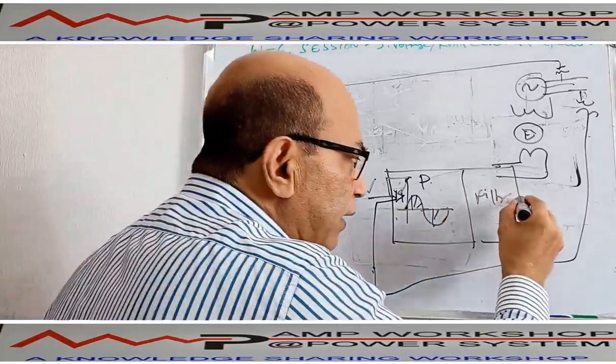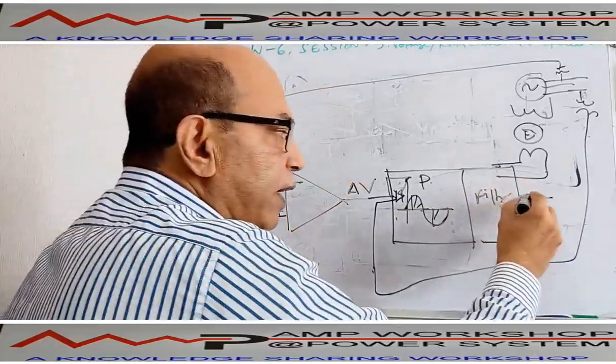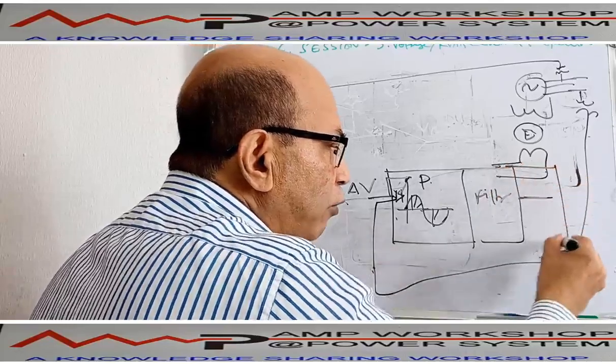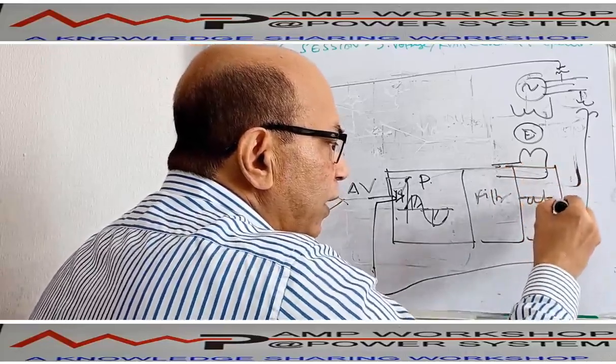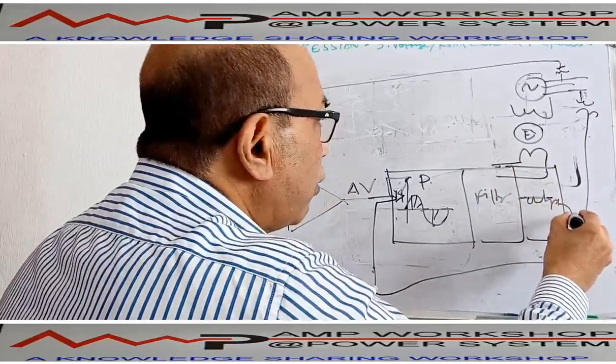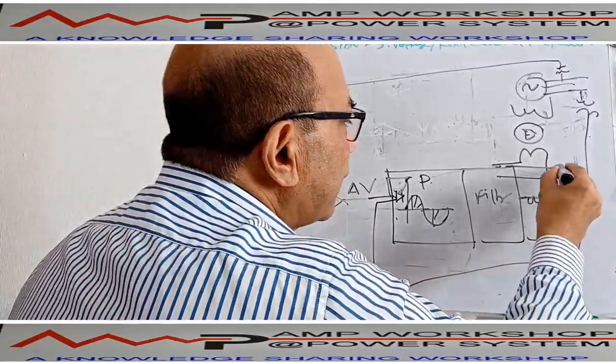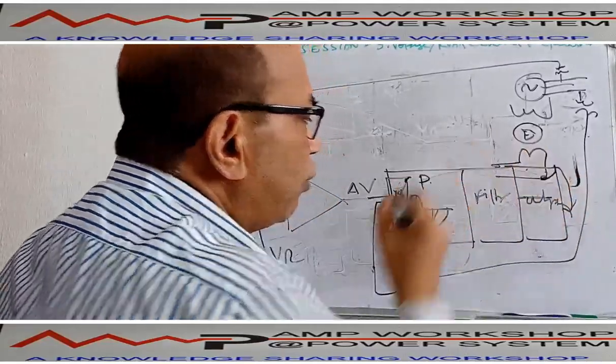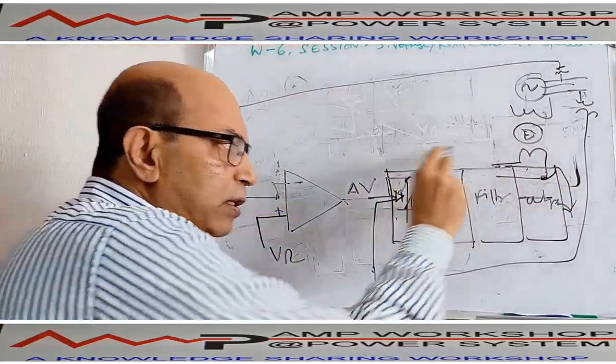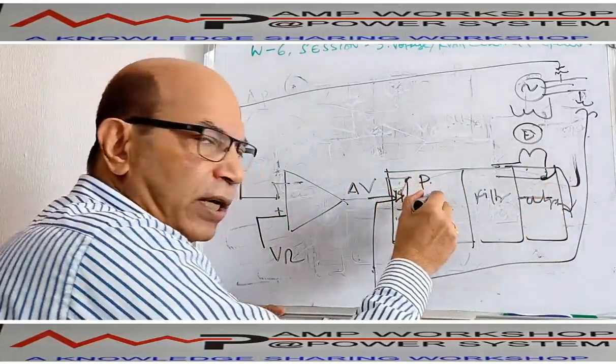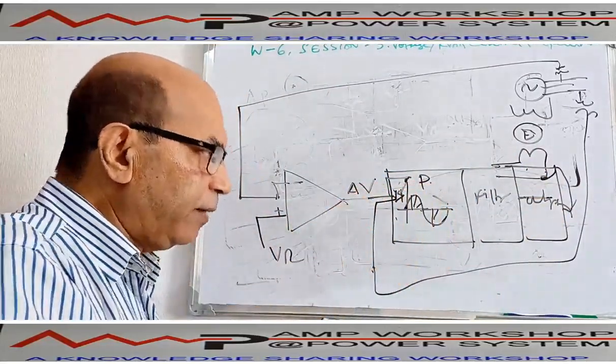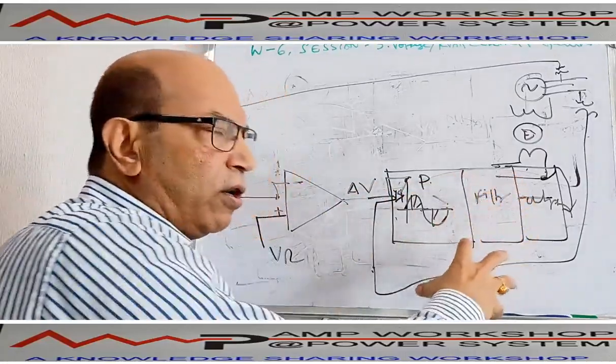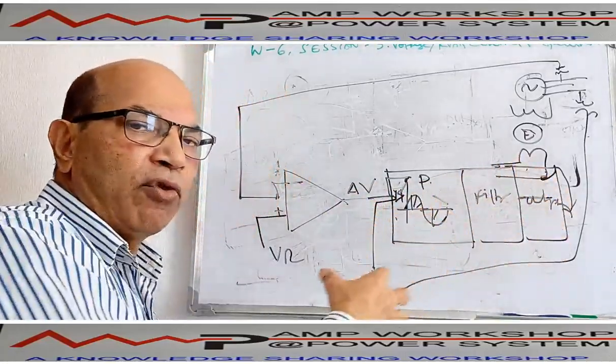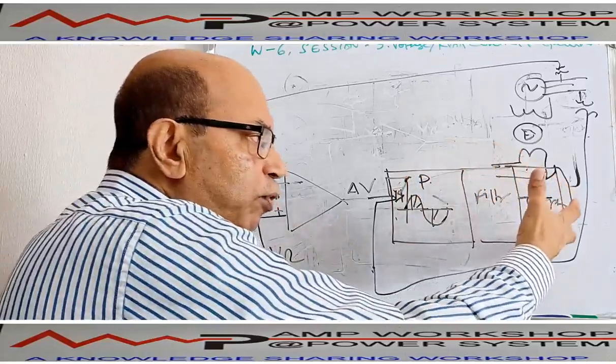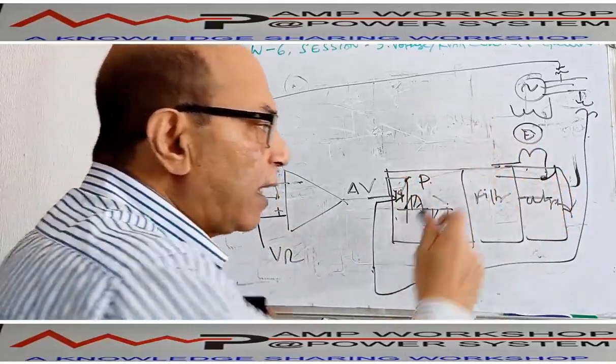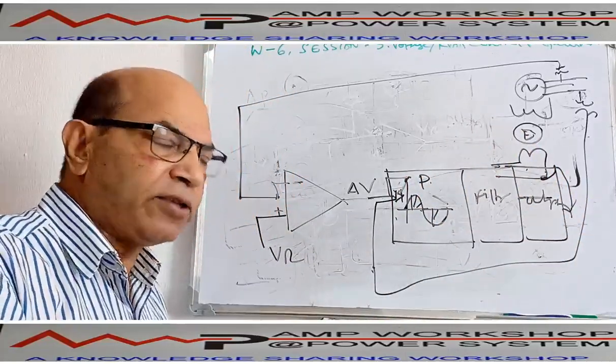Then what is this filter section doing? After the filtering, the output comes. It is an output section, and where is this output section going? It is going to the exciter field. So this control device has one input section where these two signals are received. Then it has a processor or power section with a filter, the output comes as DC, and then it goes to the output section. These are the three major sections.